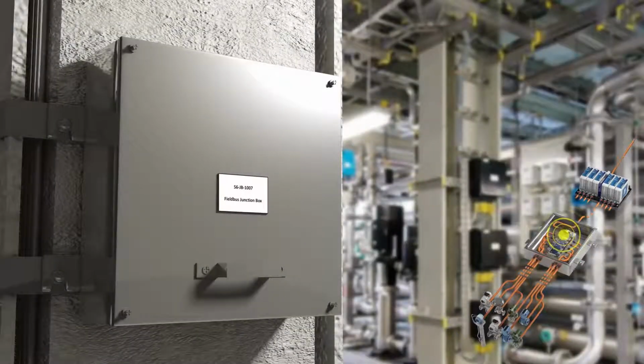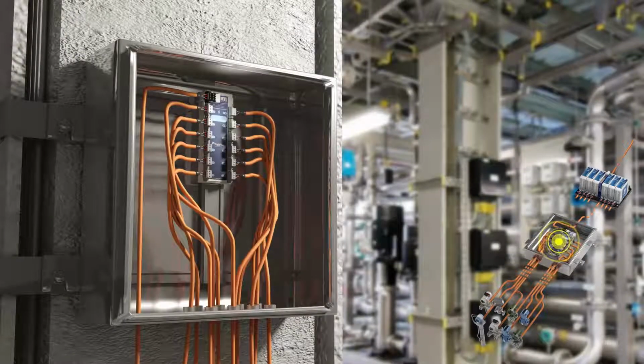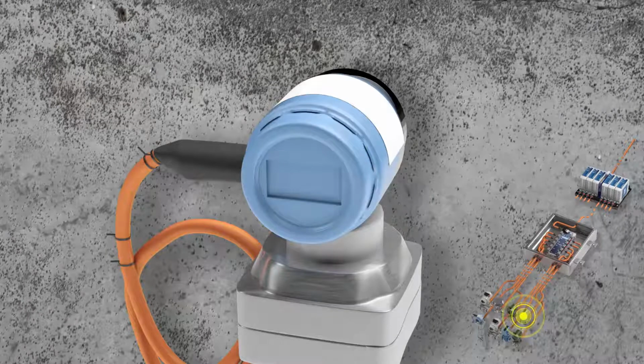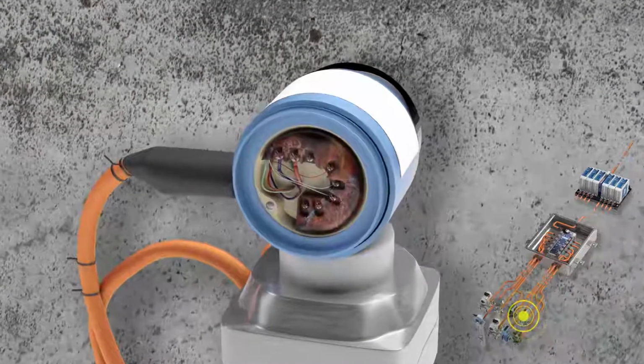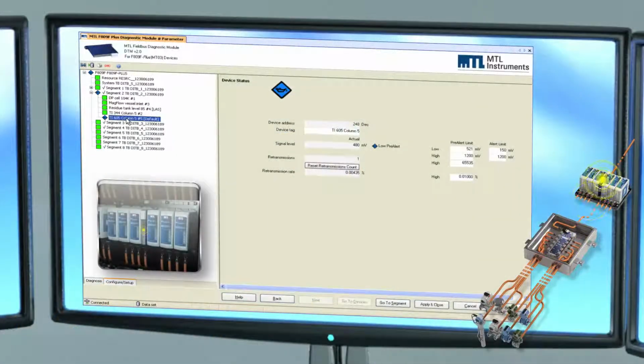As the signal level falls further, the affected device fails to respond to Fieldbus messages from the link active scheduler and retransmissions occur. This trips the retransmissions rate pre-alert limit. Although the host control system may accommodate the fault by sending message retries, immediate remedial action needs to be taken before communication with the affected field device is lost altogether.